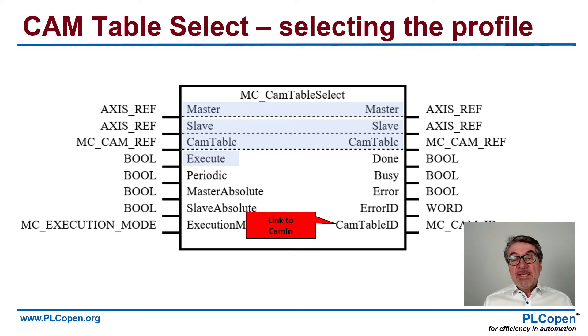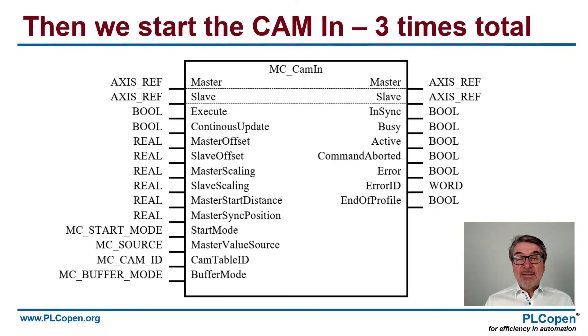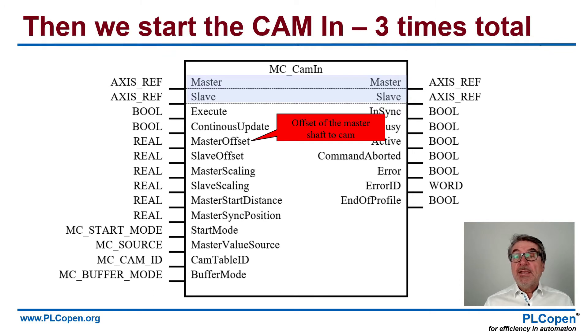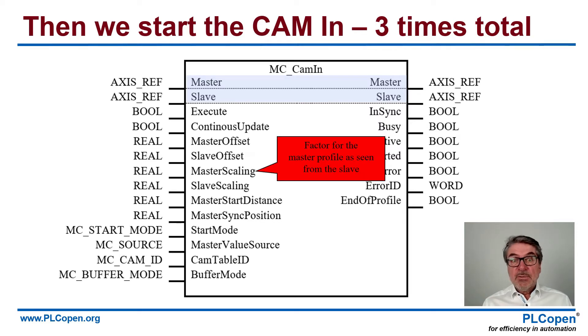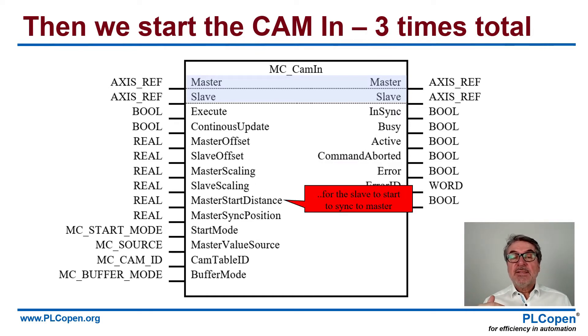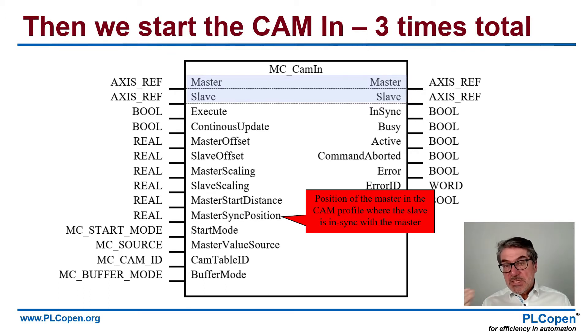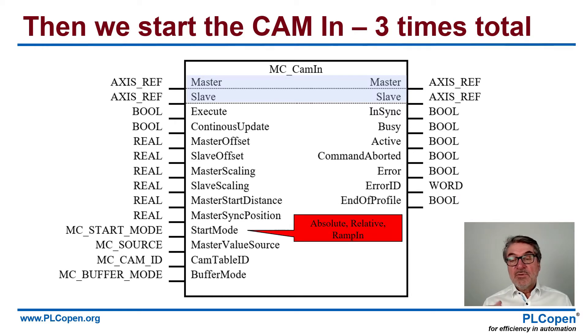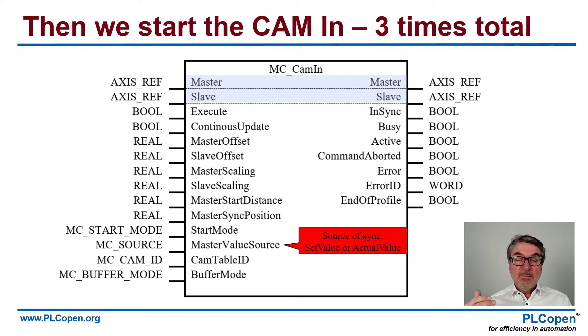What is important is the CAM table ID, which is the link to the CAM_In function block — the next function block we use — where again we see a master-slave relationship where we link the slave to the master. We do that with certain inputs where we can set the offset of the master, the offset of the slave table, a scaling from the master seen from the slave, the slave scaling factor, master start distance where we sync to the master, and a master sync position where we link sync in the profile. We have a start mode: absolute, relative ramp in. We also have the master value source — whether that's a set value or the actual value.